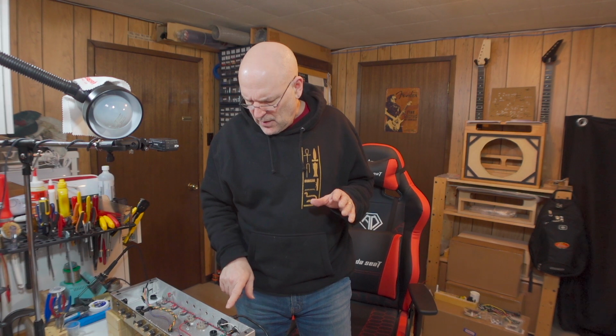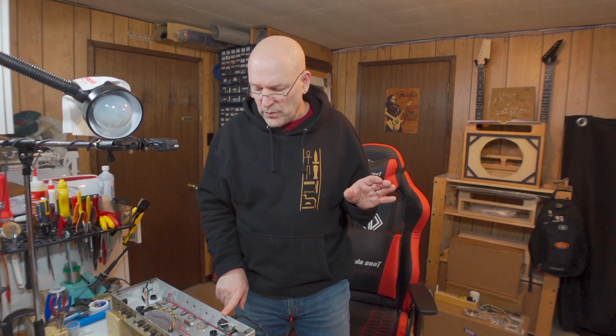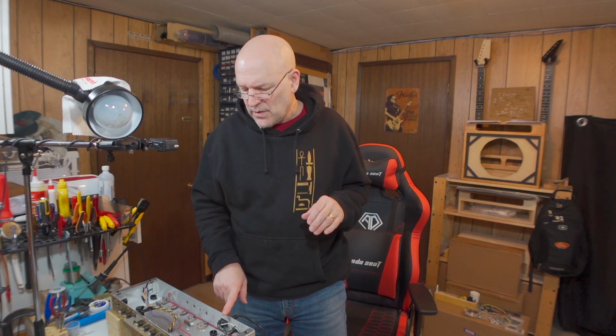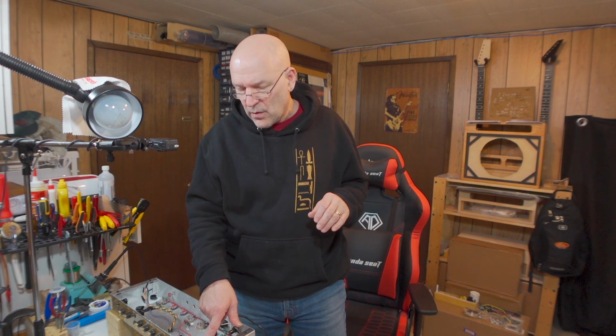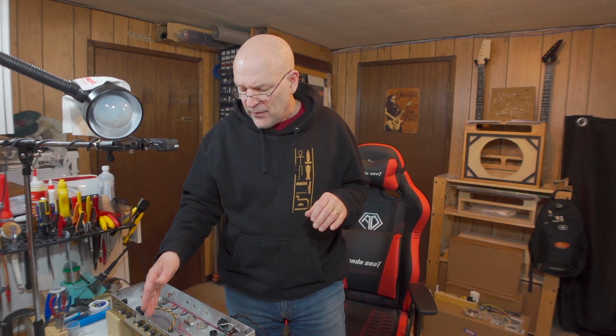And if that's okay, we will take it to full power mode, and then we will start measuring the voltages. Another thing with regard to that, with measuring the voltages, other than the incoming mains line, which will be 120 volts, or should be 120 volts, and the power across the indicator lamp, which also should be 120 volts, everything else will be coming out on the other side of the transformer. They will be AC voltages. They will be stepped up or stepped down.